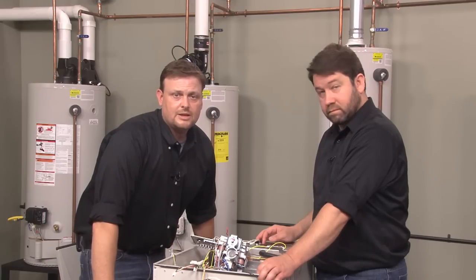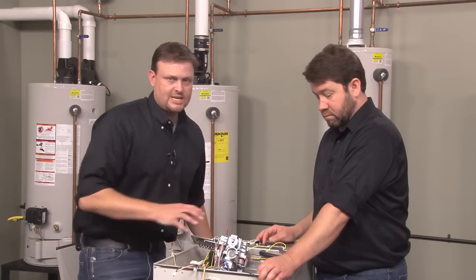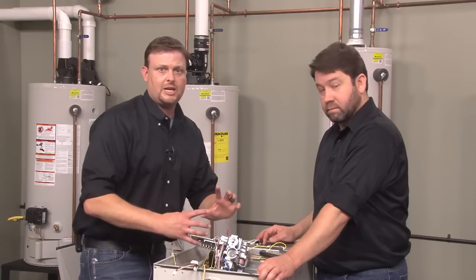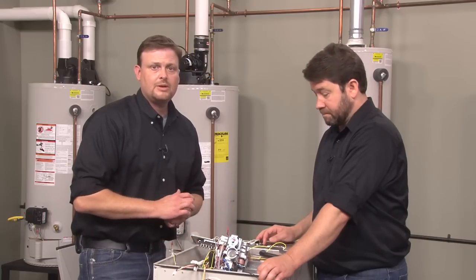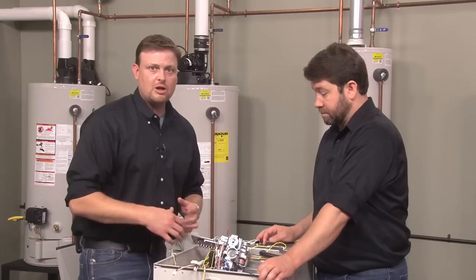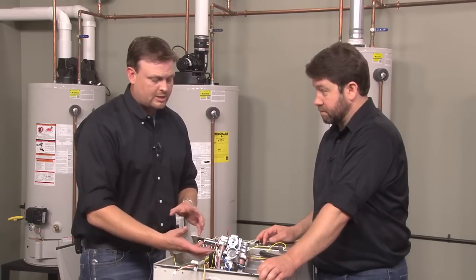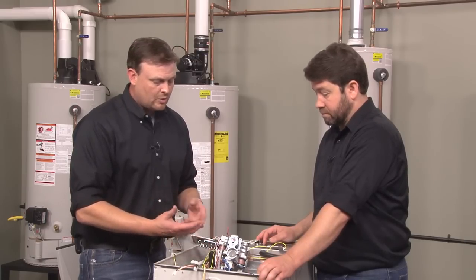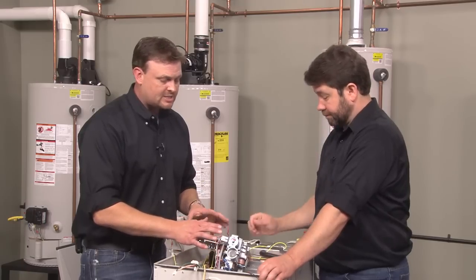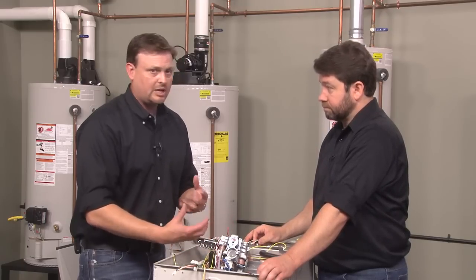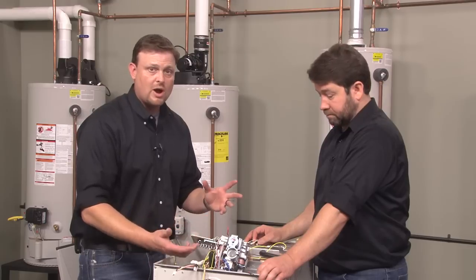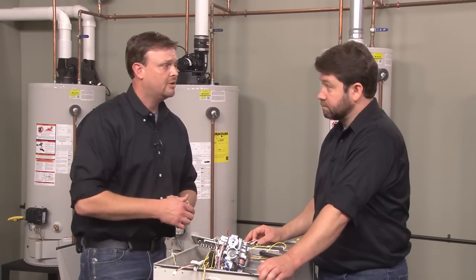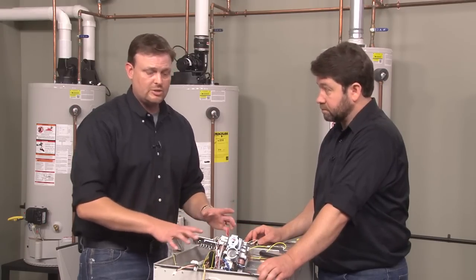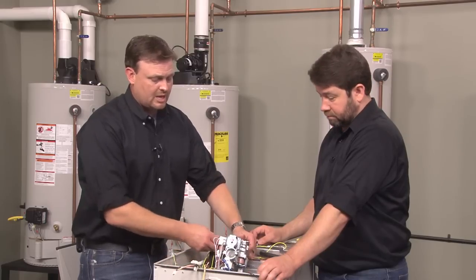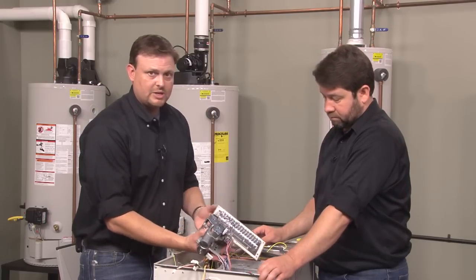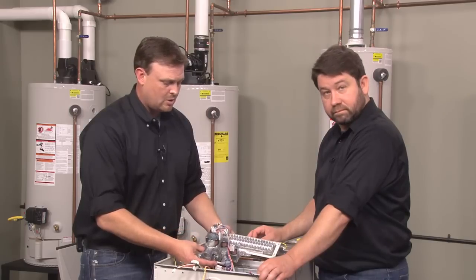We're going to take the wires off the gas valve once we get it up, because we want to talk about how you connect the gas valve. That's really the spot where you can get confused, since you can put the wrong wire with the wrong solenoid valve. We want to make sure we see and do this properly, so we'll take it off once we get the other gas valve out and walk through it.